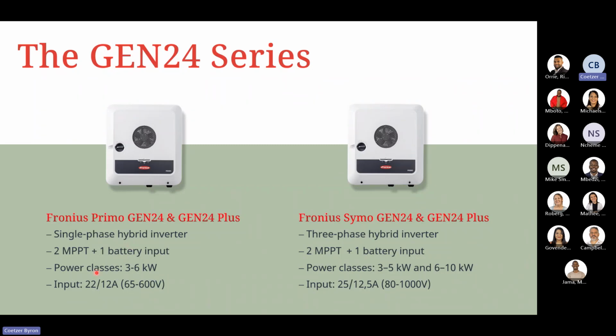Again, power class 3 to 6, but we have expanded this to 10 kilowatts coming into the country on the single phase side. And again, your input range, so we've split it between the two MPPTs. So you got 22 amps on the one and 12 amps on the other MPPT. And this is a voltage range of 65 to 600. And the way we get away with the lower voltages on the DC side is we have small DC boosters in order to achieve this lower input range for the unit itself.